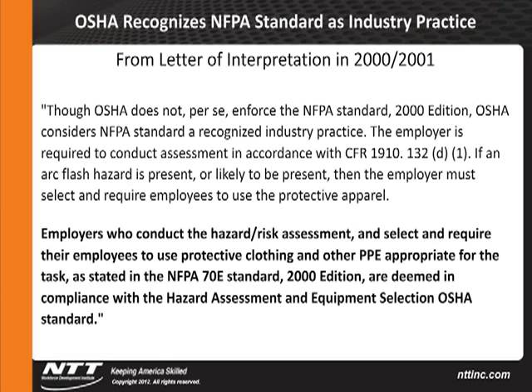The employer is required to conduct an assessment in accordance with 1910.132(d)(1), which is the PPE standard. If an arc flash hazard is present or likely to be present, then the employer must select and require employees to use the protective apparel. So this is the important part. Employers who conduct a hazard risk assessment and select and require their employees to use protective clothing and other PPE appropriate for the task, as stated in the NFPA 70E standard, are deemed in compliance with the hazard assessment and equipment selection OSHA standard.